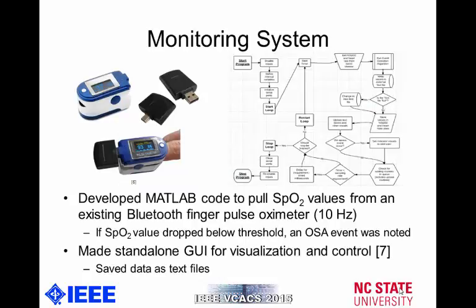Our monitoring system uses the commercially available CONTEC pulse oximeter, and we designed MATLAB code to pull the SpO2 values from this existing device. The device came with its own custom software, but using a packet sniffer device, we reverse engineered the information this device sent to the computer, and from it we were able to take samples of blood SpO2 at a rate of 10 Hz. If the user's SpO2 value dropped below a certain value based on that Medicare definition, then an obstructive apnea event could be noted based on how long or for what percentage of time it dropped below that value. Additionally, we made a standalone GUI for visualization and control — controlling things like deciding what value the patient's threshold would be — and this GUI would also save the data as text files so that they could be reviewed by physicians later on.